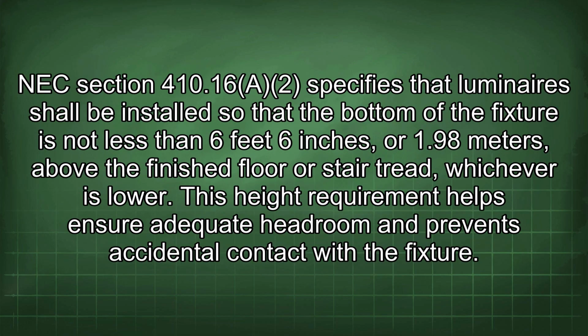NEC Section 410.16a specifies that luminaires shall be installed so that the bottom of the fixture is not less than 6 feet 6 inches, or 1.98 meters, above the finished floor or stair tread, whichever is lower. This height requirement helps ensure adequate headroom and prevents accidental contact with the fixture.